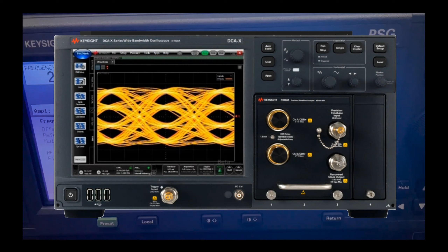I'm going to talk to you about the mainframe user time-based calibration that's on the DCA N1060 module and on the DCA. Even if you've bought a new DCA and a new DCA module, you should be performing this user time-based calibration when you're trying to get best accuracy. That means things like EOJ, anything with PAM4, anything that's in 56 gigabaud or higher. It's highly recommended to get the best repeatable results by doing this procedure.